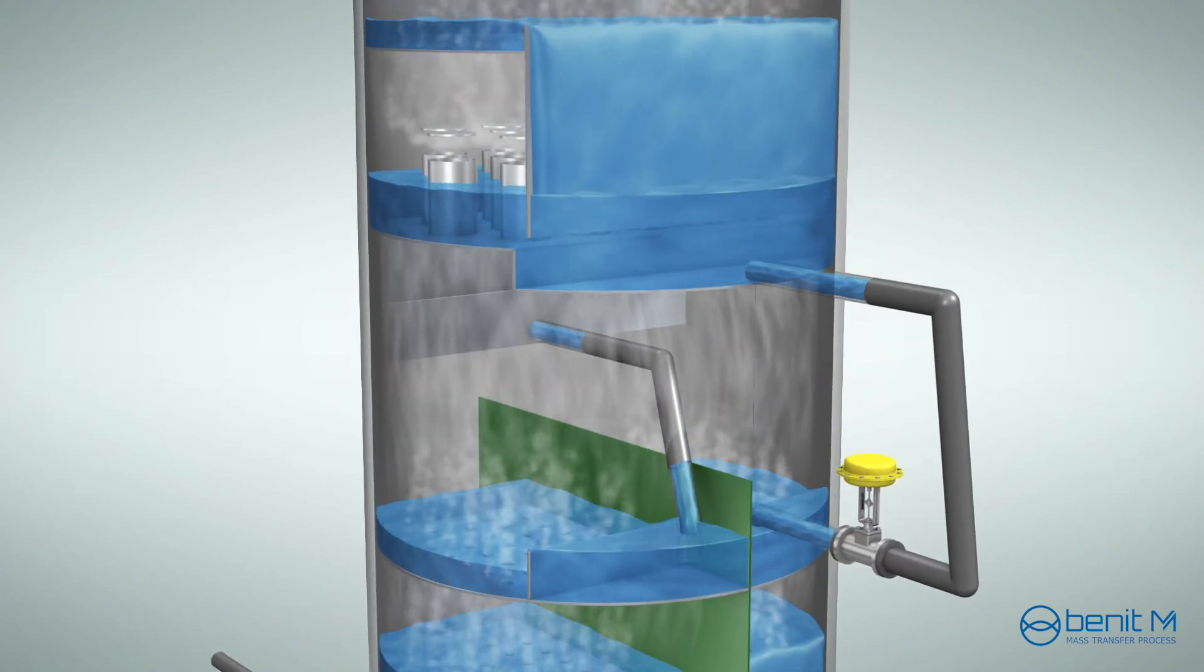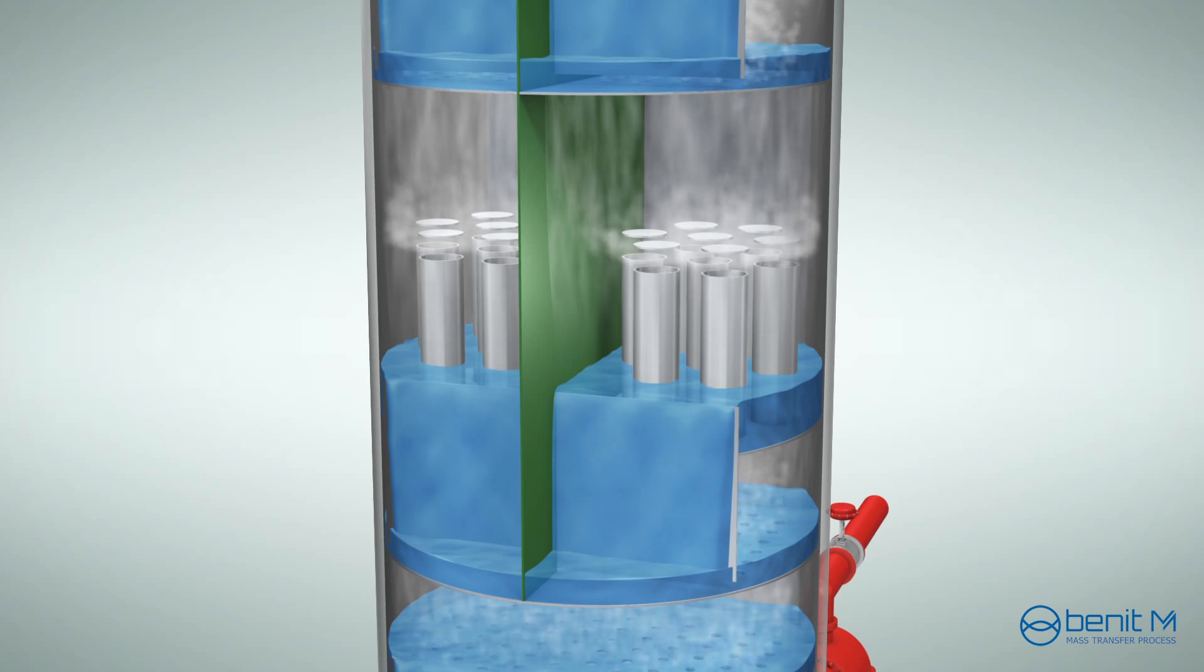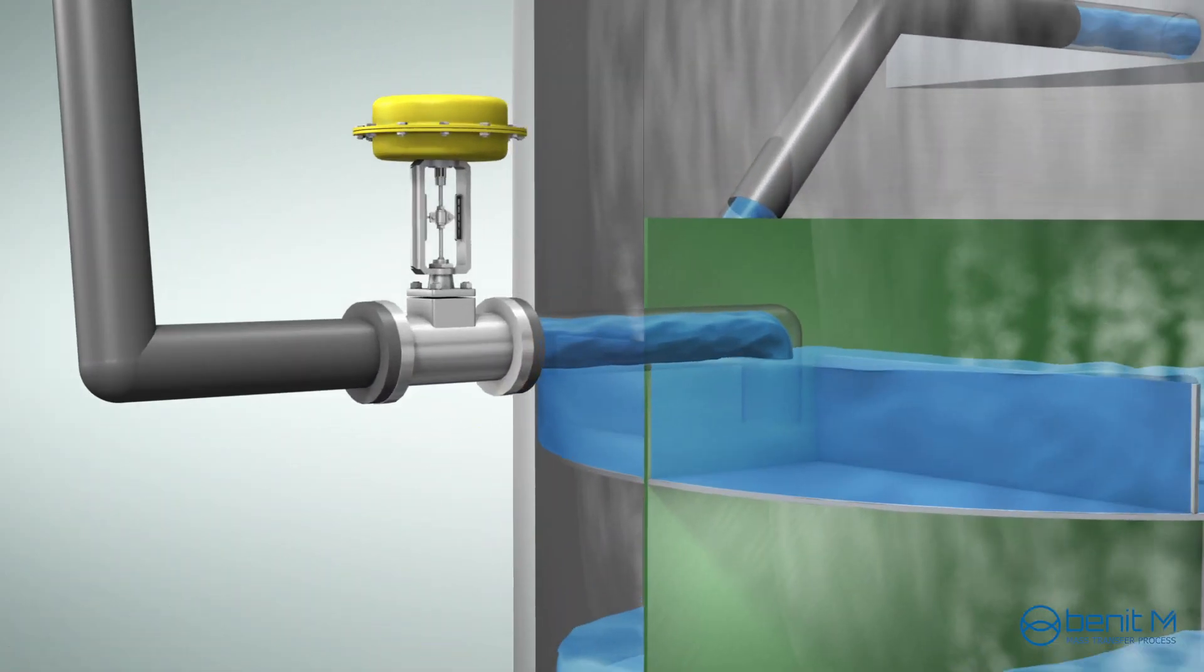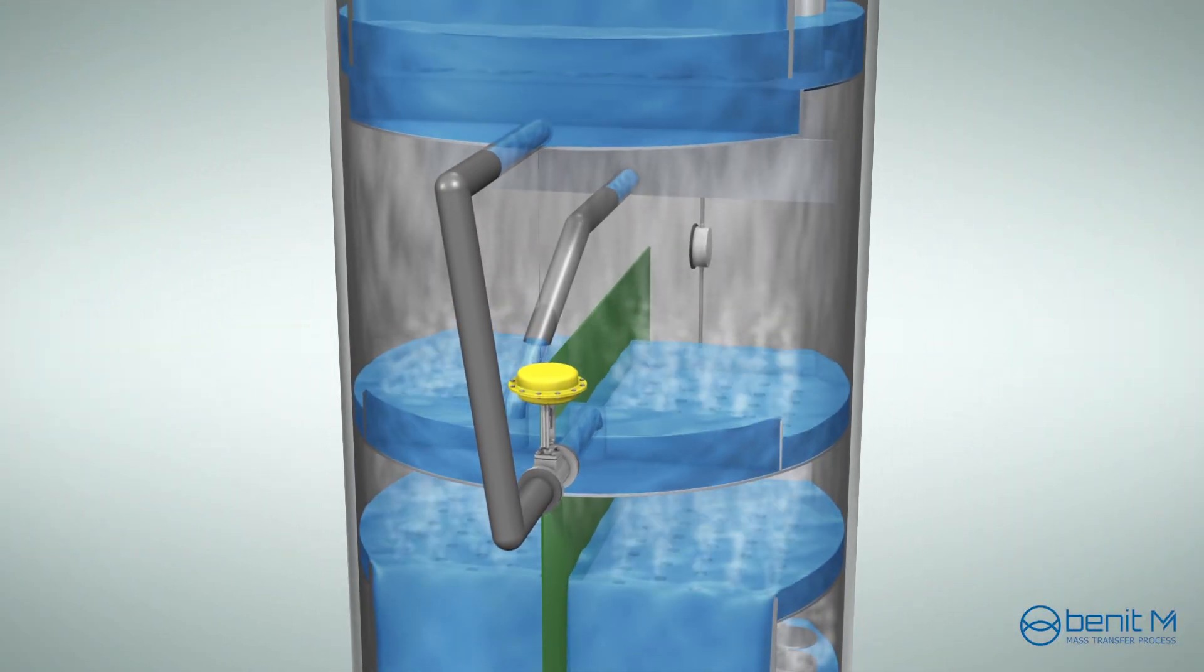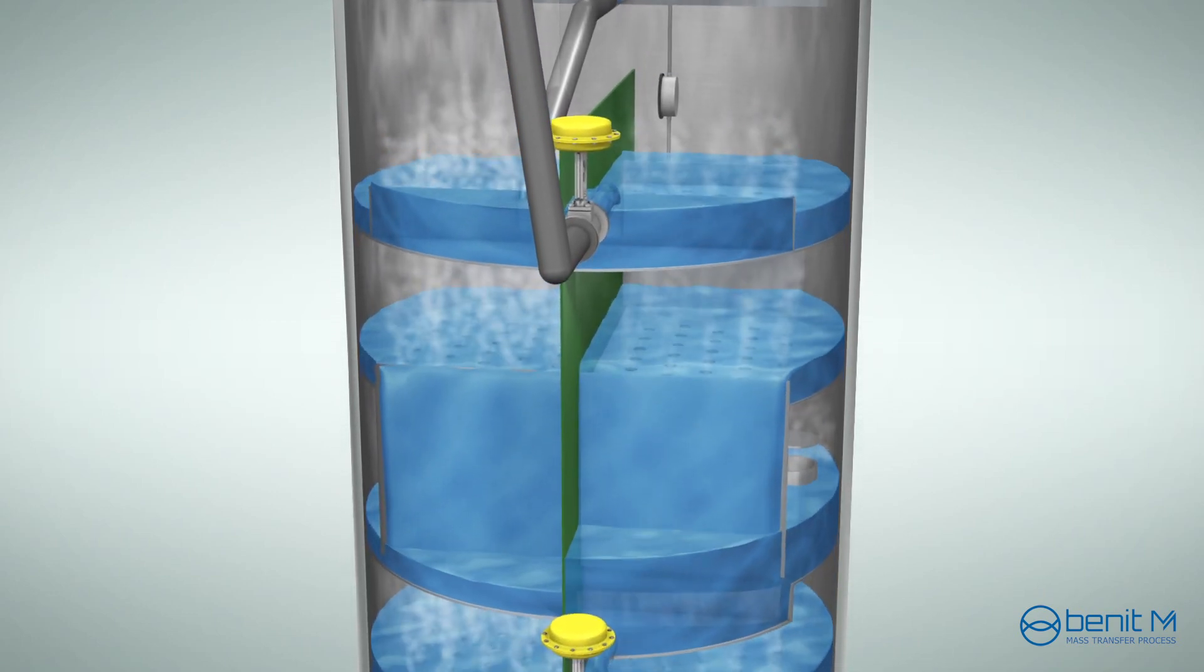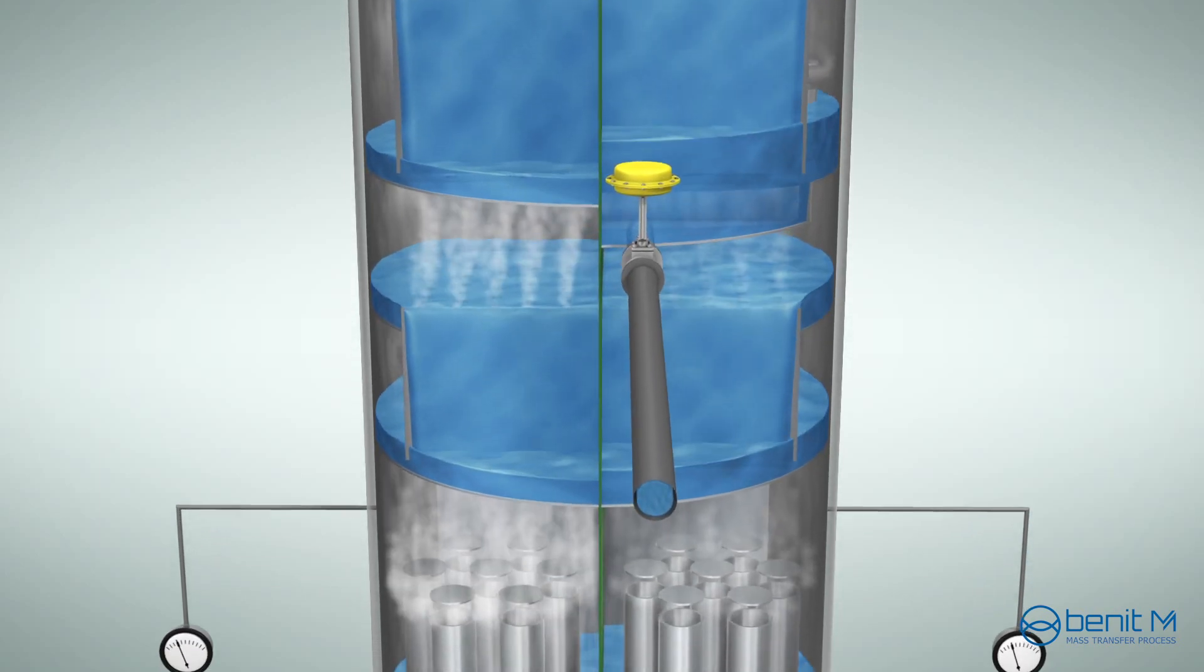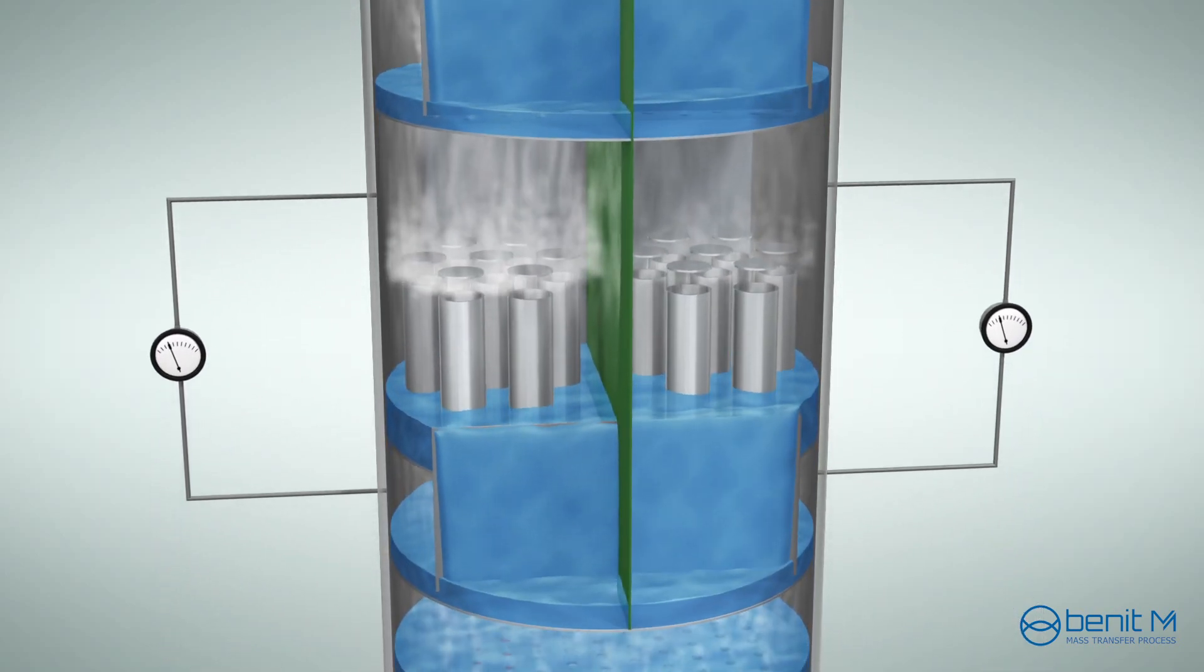When any operating conditions are changed, both liquid split ratio and vapor split ratios need to be tuned to maintain the desired performance. Operator can adjust the liquid split ratio as dividing wall columns are normally equipped with an active liquid splitter. When the liquid load increases in main fractionation section, the liquid load in pre-fractionation section is decreased because the total reflux rate remains the same.